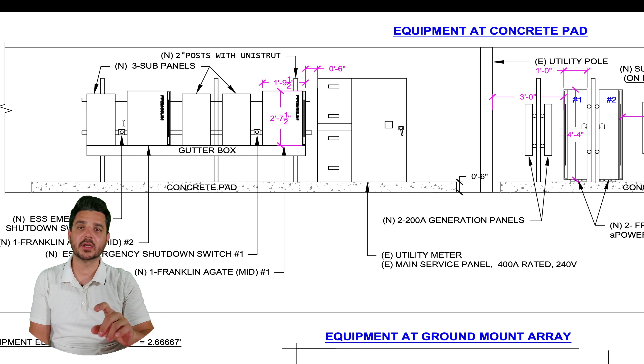It's completely safe. The array has shut down, the batteries are shut down, there's no backup initiating, the generator won't come on, and then they can go to the main service and shut off loads as they want, or open up the sub panels and shut off loads as they want. I find these to be far more valuable than switchblade disconnects, as a first responder is just going to run around shutting off a bunch of switchblade disconnects and breakers, whereas this, they can turn a knob or push a button, lock it, and it's shut off, right? They do have, most of these have a protective cover, and when you shut it off, you can tag it on the knob so it's locked into place and can't be reinitiated.